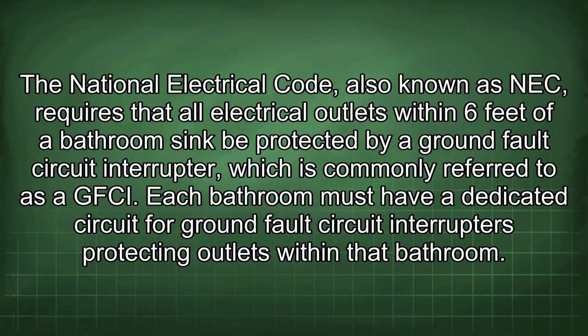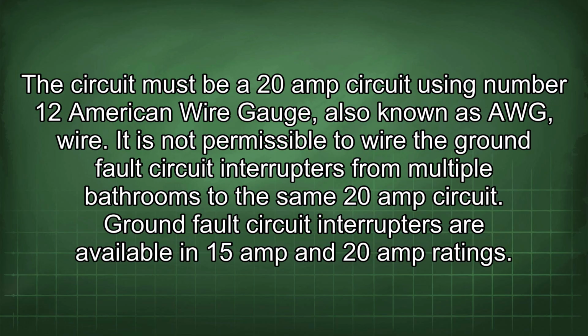The National Electrical Code, also known as NEC, requires that all electrical outlets within 6 feet of a bathroom sink be protected by a ground fault circuit interrupter, commonly referred to as a GFCI. Each bathroom must have a dedicated circuit for ground fault circuit interrupters protecting outlets within that bathroom. The circuit must be a 20 amp circuit using number 12 American wire gauge, also known as AWG wire.